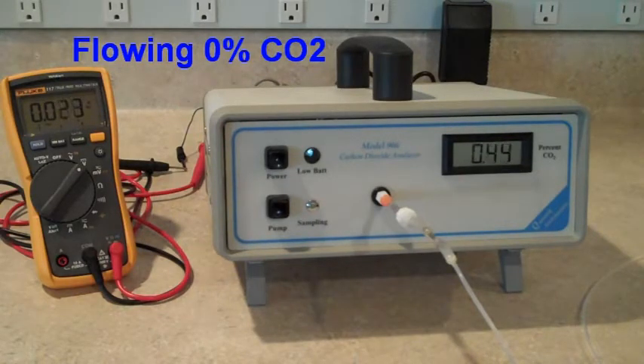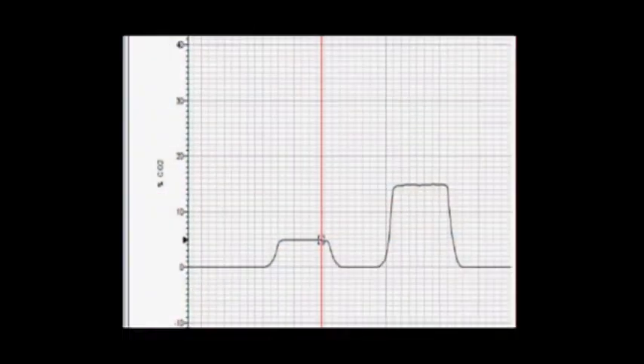And finally, we're going to flow pure nitrogen through it to get the analyzer back down to zero. Now let's take a look at the software.